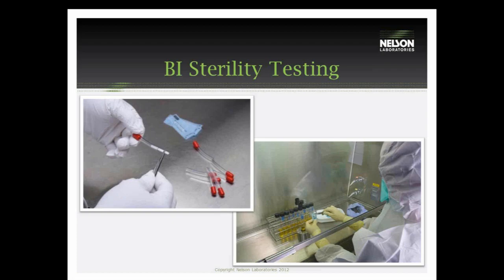Again, here we're looking for no-growth results. We want the BIs to die in the half cycle to help demonstrate that 12-log reduction requirement.